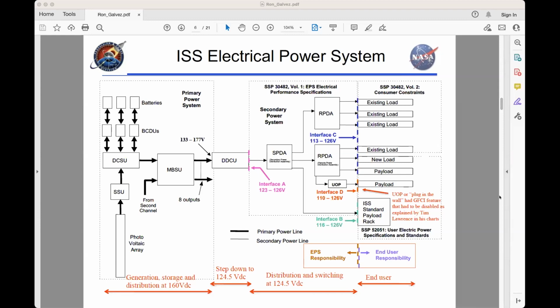I pointed there towards the bottom, in what appears orange, to the issue Tim pointed out in his charts with the UOP. The UOP basically had a ground fault circuit interrupter, kind of like what you have in your bathroom, and it was tripping, as Tim pointed out. There was a lot of equipment with leakage in excess of the requirement, so a great safety function ended up being detrimental to the point that it became unusable. We ended up having to go in and actually clip the circuit out, so no UOPs on station have this GFCI function anymore.